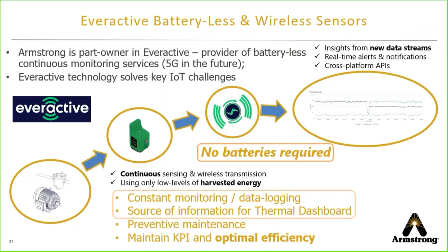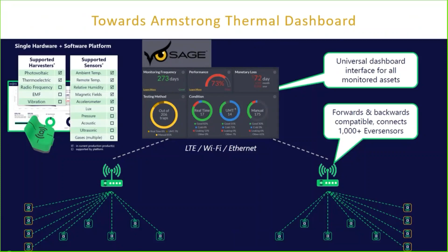Because we could test a trap today, that trap could fail tomorrow, and then 363 days later, we'll test that trap again. In the meantime, we've lost a lot of CO2, we've lost a lot of energy. So one way to do that is to remote monitor with a wireless, batteryless technology, deliver that to a dashboard that you can use, you can see, that provides you alerts when a trap has failed, delivers reports on how much energy is wasted to help you determine your ROI, and that is flexible enough to allow you to manage that network in the simplest possible way.